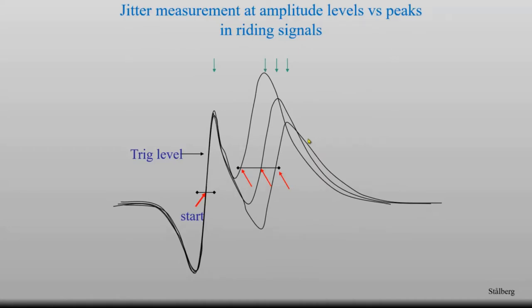But in a situation where signals are riding on each other — not uncommonly seen in concentric needle electrode recordings — the original amplitude level technique measures on different parts of the signal. This signal is measured in its middle and another part is measured closer to the positive peak. Whereas if we use peak measurements, we measure on the peaks independent of the riding phenomenon.